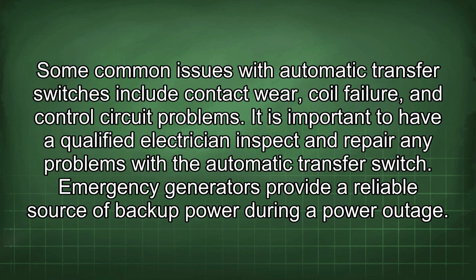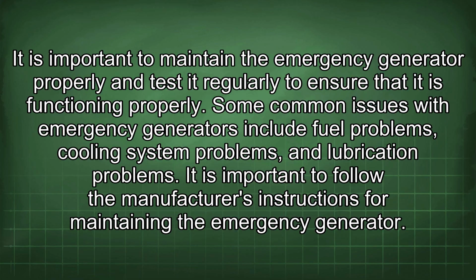Emergency generators provide a reliable source of backup power during a power outage. It is important to maintain the emergency generator properly and test it regularly to ensure that it is functioning properly. Some common issues with emergency generators include fuel problems, cooling system problems, and lubrication problems. It is important to follow the manufacturer's instructions for maintaining the emergency generator.